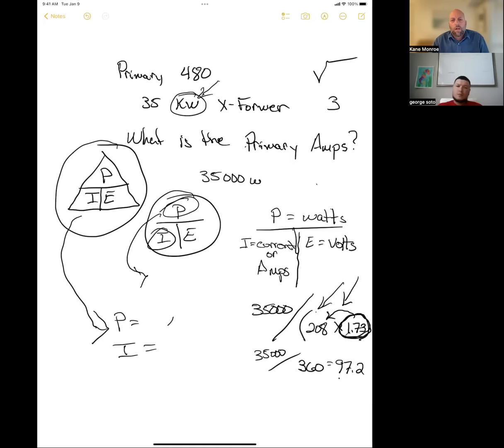Now, if they want to know your overcurrent protection on your secondary side, you need to take this and multiply it times 1.25 to get your breaker size. 1.25? Yeah, it's 125%. Where do you get that? Hold on, let me get my code book. All right, here we go. And that would be your overcurrent protection for the transformer, secondary side. So that would be feeding a load center, for example? Exactly. We already know that the secondary side is 208.